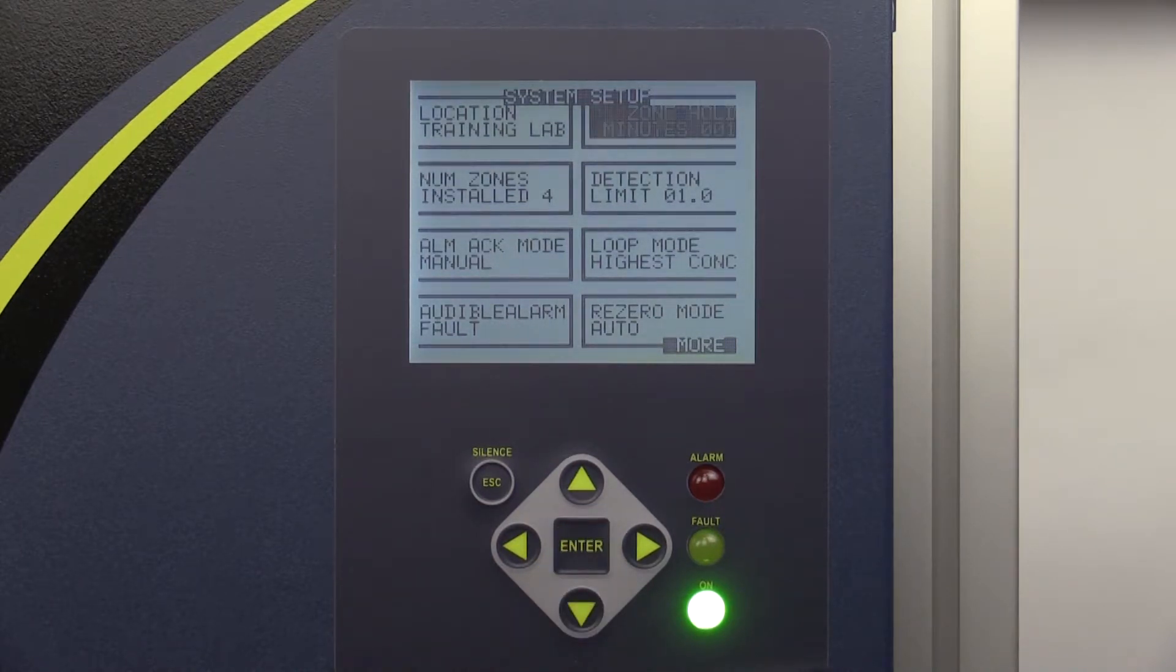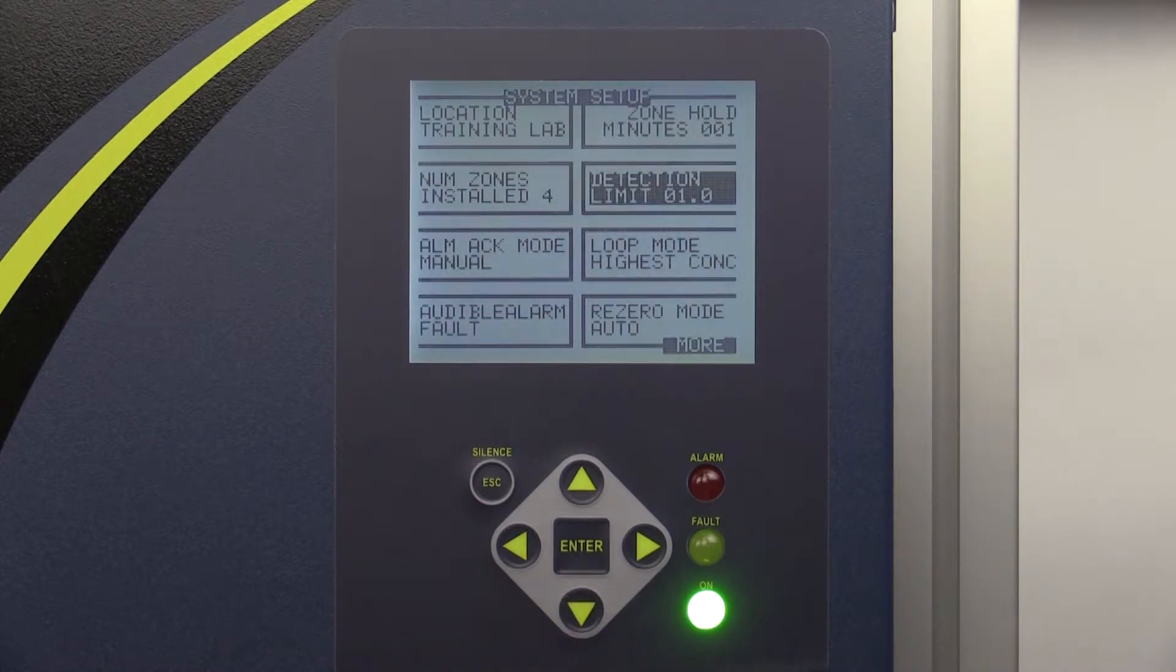The detection limit tab allows you to set the minimum PPM reading that will be registered on the display. It can be set between 1 and 99 PPM. Any PPM reading below the designated value will be interpreted and displayed by the monitor as 0.